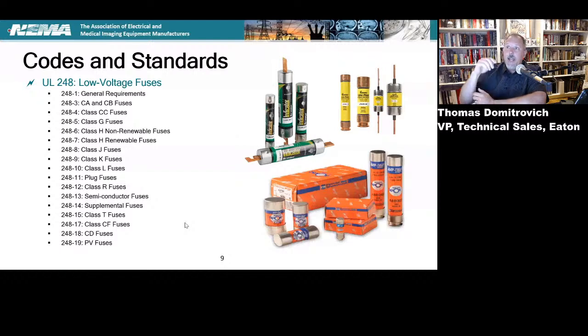So each individual fuse class is broken out into a different standard. You have UL 248-1, which is your general requirements. It's just like the National Electrical Code. You have the general requirements, and then you have the specific requirements for each of those classes of fuse. And the big differentiator, outside of the current limiting performance of those devices, is the footprint, the size, and all of the rejection features that might be included in each of those classifications.